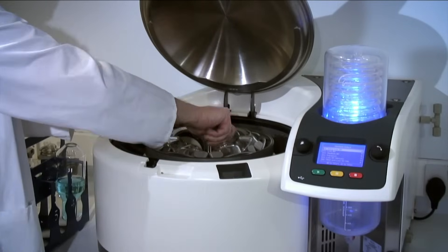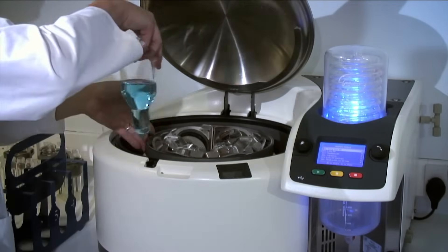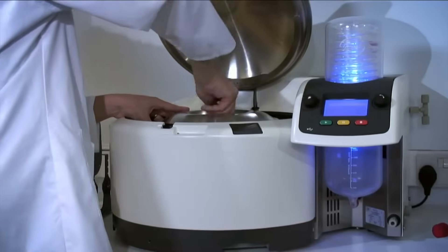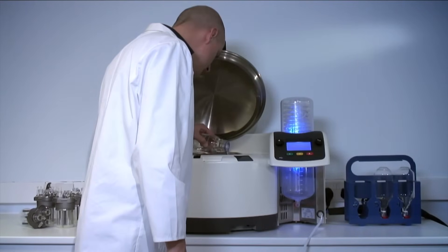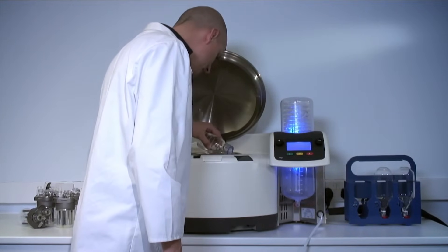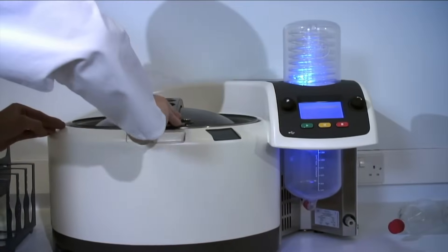Using the Rocket is simple. Load your flasks or pucks of tubes into the rotor. Secure the inner lid. Check the water level. In normal operation, the Rocket will need an addition of less than 50 milliliters of water per day.